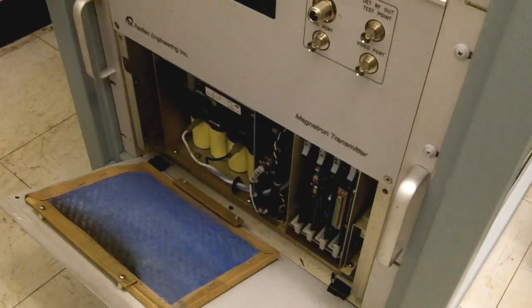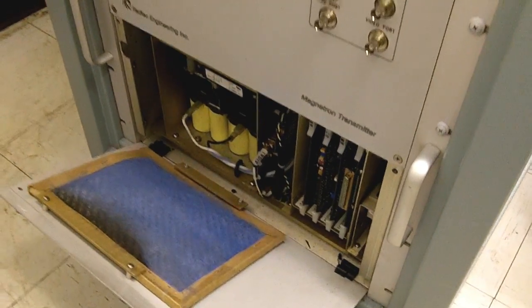And call up tech support. There's another fan that's inside this high voltage power supply that's probably bad too, but you won't see it from here, you gotta open the whole thing up. So we think we figured out a major problem. We have like four dead fans that need to be replaced. That's why the transmitter is going to standby protection mode, because you don't want to burn this tube up.